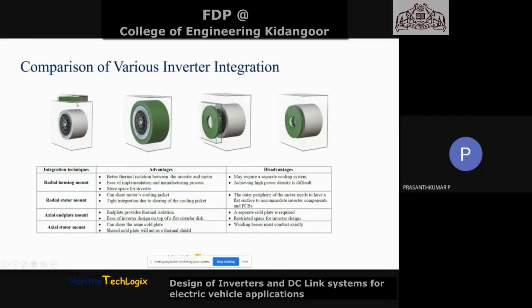They have placed the inverter radially, and one of the main reasons is to have better thermal isolation between the inverter and motor. If the motor is developing a lot of heat, causing a temperature rise, placing the inverter very close to the motor will not be a good idea, as it will create problems for inverter operation. Many other cases also drive this decision, for example when there is more electromagnetic radiation created from the motor housing or motor system, placing the inverter very close to the electric motor may not be the right idea.